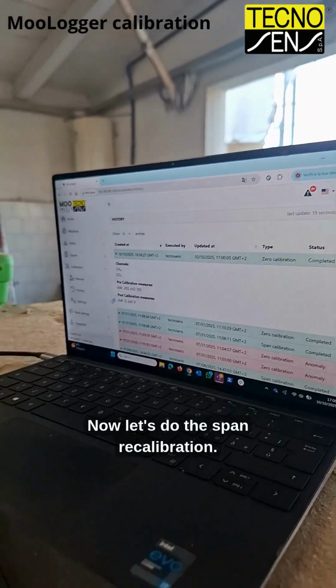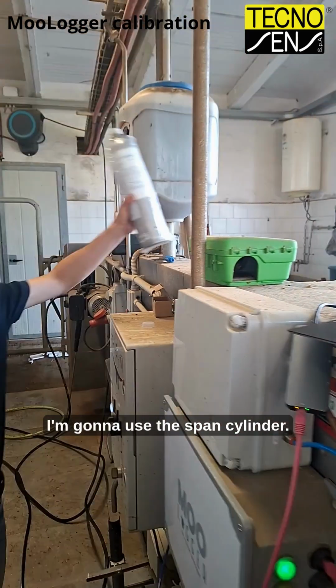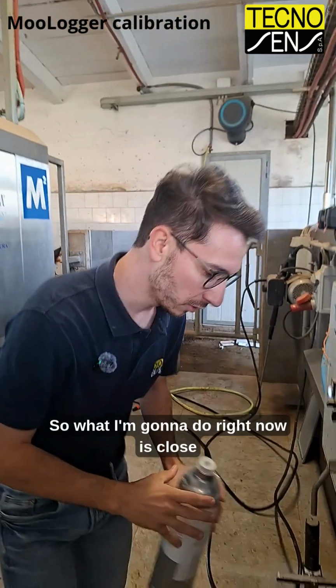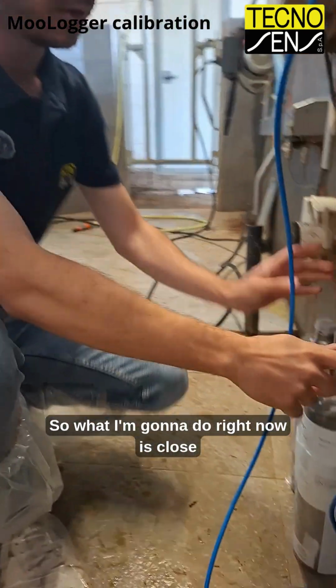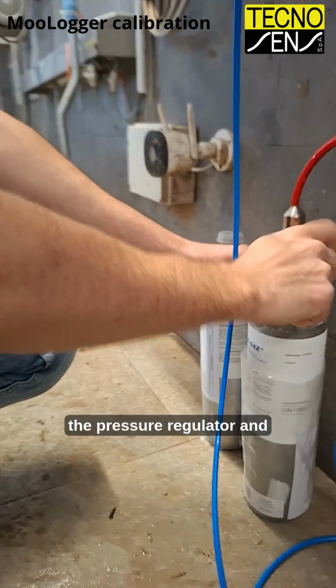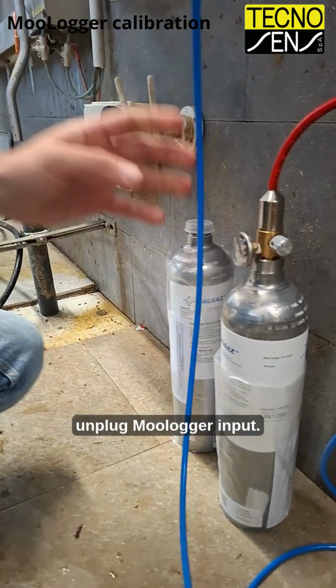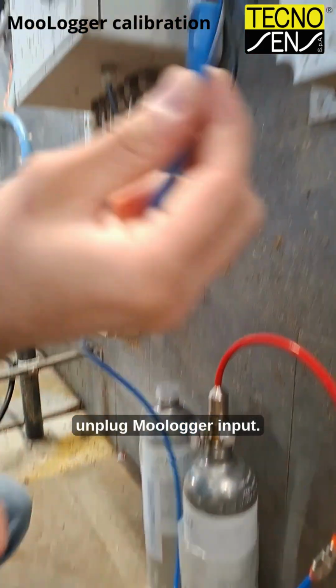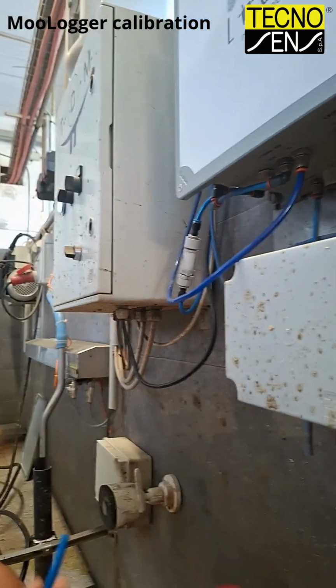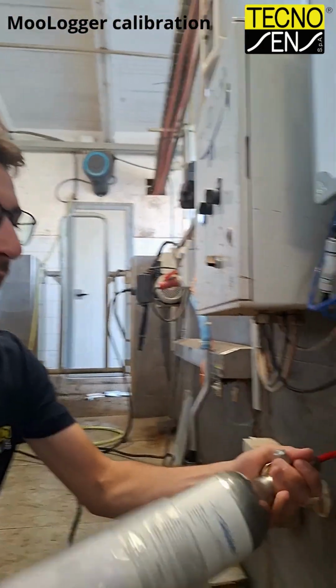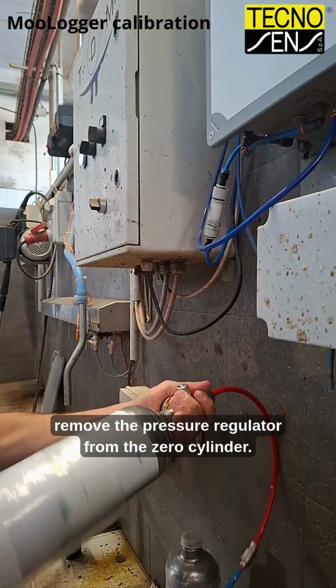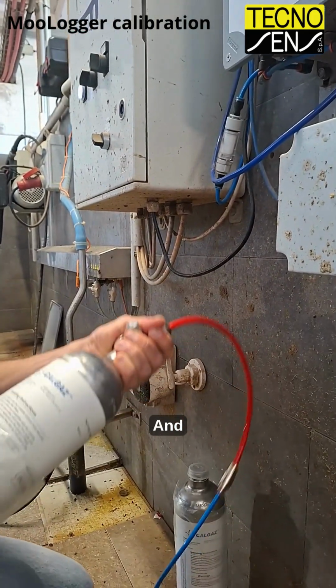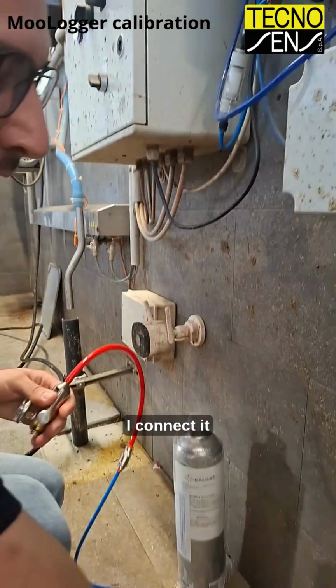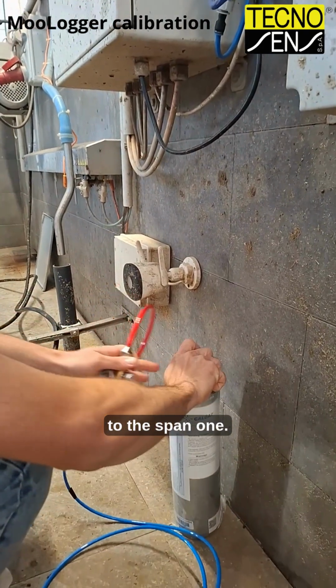Now let's do the span recalibration. I'm gonna use the span cylinder. So what I'm gonna do right now is close the pressure regulator and unplug the MooLogger input. Then I remove the pressure regulator from the 0 cylinder and I connect it to the span one.